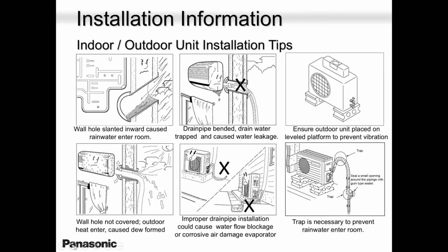These are the tips that you need to pay attention to. They are very simple tips, but they can cause problems if you don't obey them, especially this guy here. You see this guy, he put a spirit level. If this unit is not level, that oil will not come back easily to the compressor, and you may lose that compressor within 6 months' time. And then what? Oh, I bought a bad unit. I bought a bad brand. I get these calls. No, it's not that. We have units running for 10 years now, 10 years and counting.